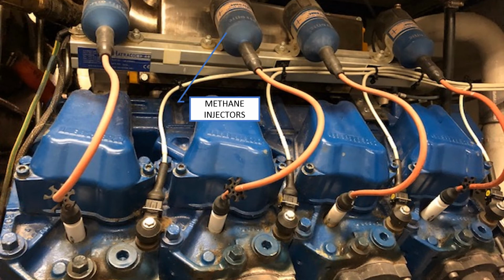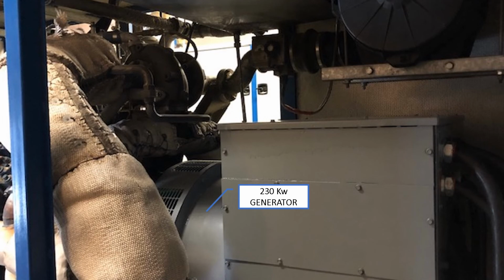Combined heat and power units were manufactured by Tech 3 Solutions. These engines are designed to run on biogas as well as natural gas. They're capable of producing 230 kilowatts of power, and there are 2 of these units. The engines on each of the combined heat and power units are V8 engines with methane injectors. They're very standard engines for heavy loading equipment, and the engine itself is produced by Liebherr. As you can see here, the generators are coupled onto the back of each engine. As I mentioned earlier, each generator can produce roughly 230 kilowatts of power.